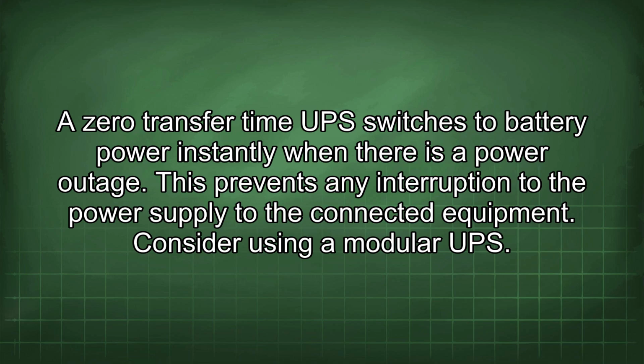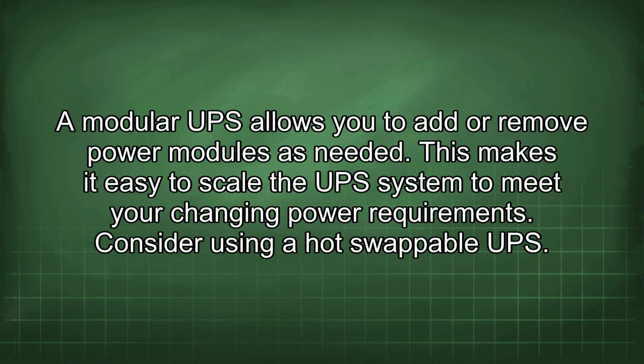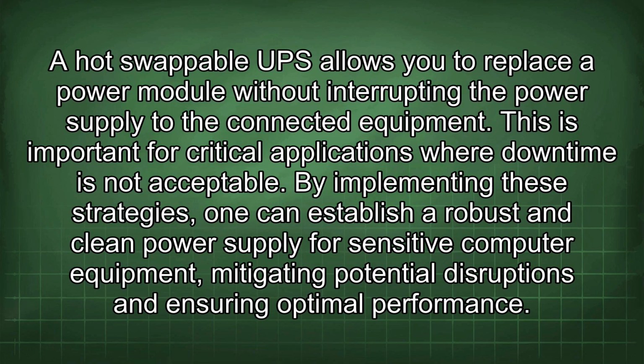Consider using a modular UPS. A modular UPS allows you to add or remove power modules as needed. This makes it easy to scale the UPS system to meet your changing power requirements. Consider using a hot swappable UPS. A hot swappable UPS allows you to replace a power module without interrupting the power supply to the connected equipment. This is important for critical applications where downtime is not acceptable.